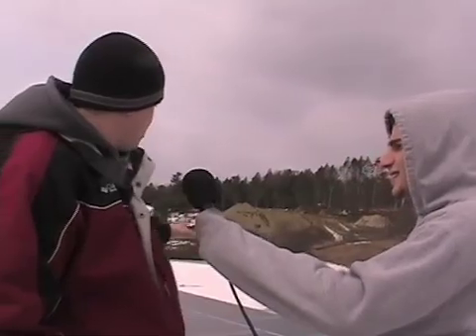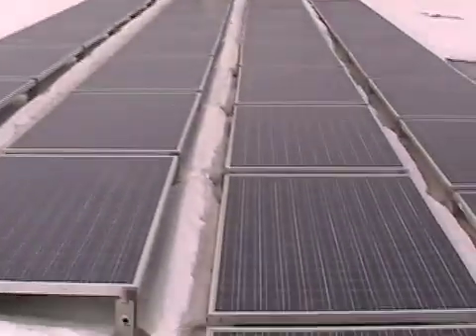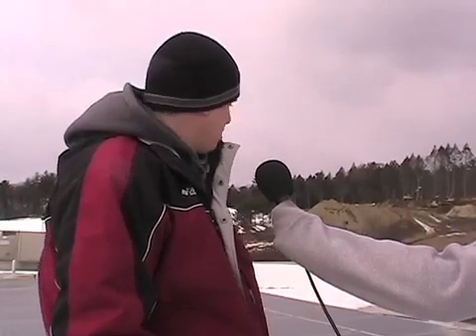So we're on the roof where the solar panels are — can you tell us a little about how it's built and set up? It consists of 33 panels, all about 300 watts apiece, making up a 10 kilowatt system. It's a ballasted system, which means it's not actually fastened to the roof — they're all linked together and their own weight holds them down. They're not at a perfectly optimal angle, but it's the best we can do with wind loading. At the end we have a data acquisition system that monitors wind speed, sun intensity, and other factors, routes the data down to a box where it's interpreted and reviewed.